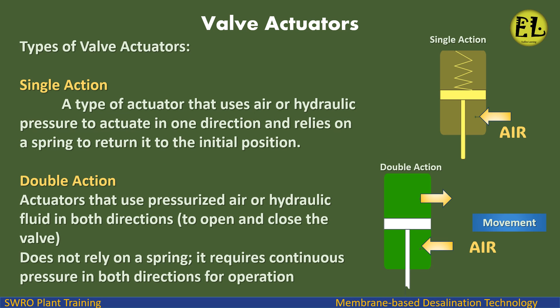Types of valve actuators. Single action: a type of actuator that uses air or hydraulic pressure to actuate in one direction and relies on a spring to return it to the initial position. Double action: actuators that use pressurized air or hydraulic fluid in both directions to open and close the valve; does not rely on a spring and requires continuous pressure in both directions for operation.